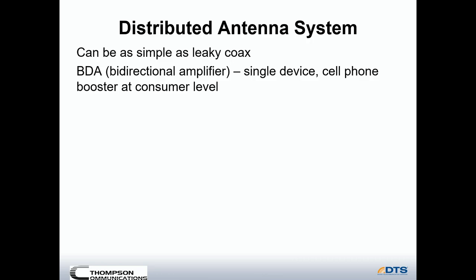A DAS can be as simple as a piece of leaky coax — a piece of coax that has perforations in the outer jacket to allow the signal to leak out, similar to a soaker hose that has a number of pinholes in it. These are often used in tunnels or elevator shafts.